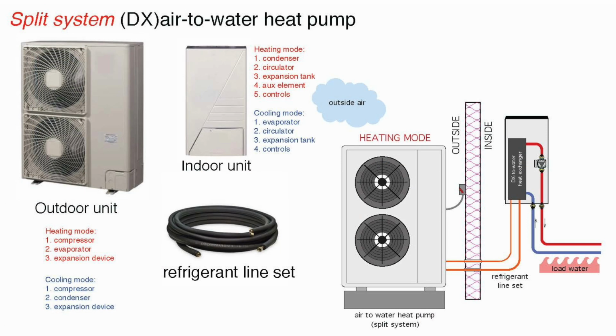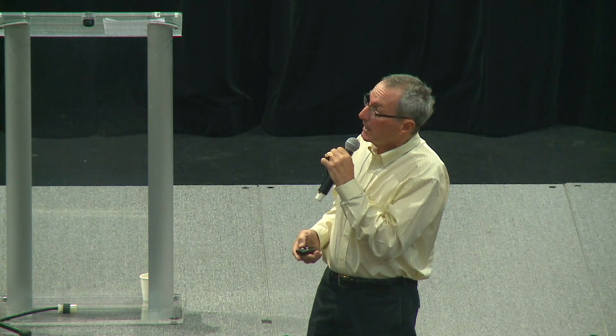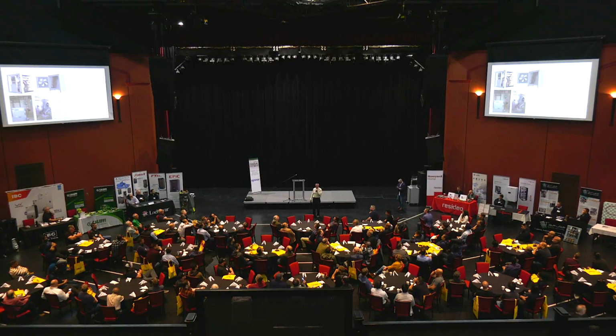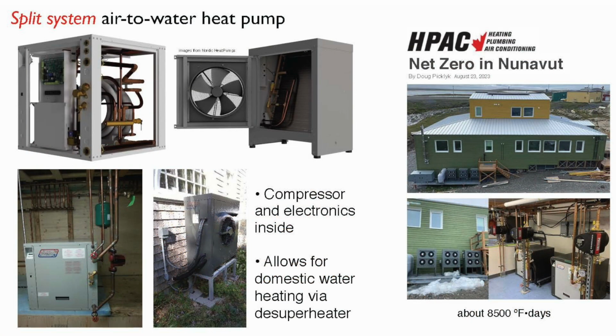And then there's also a DX or refrigerant split. This is like a standard AC unit where you've got an indoor and an outdoor unit and you've got refrigerant tubing between them. So you would need some basic refrigeration skills and tools to set these systems up. Here's a Canadian product, Nordic Heat Pumps. It's built over in Maritime, Canada. And it's a split system.